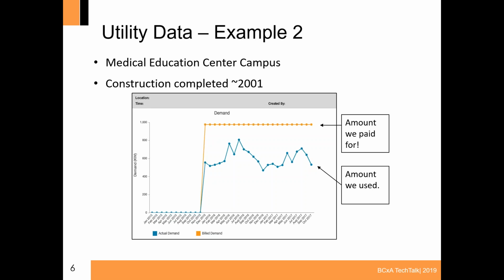It's a very standard procedure. Here's what we, the A&E firm, believe you're going to use in this building. Well, those are almost always estimated high because nobody ever got fired for putting in too much capacity. Unfortunately, the power company takes it verbatim and they say, well, you told us it was going to be this load. We put in a 1,000 kVA transformer. Now you're telling us you want less demand, but we've already spent the money and put in that big transformer.